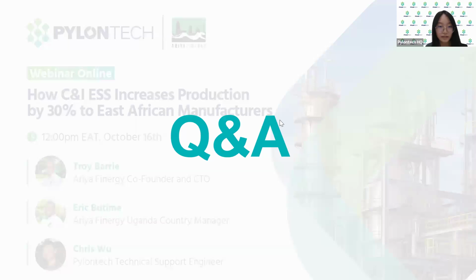Next question from Drake about how we carry out module level and rack level calibration. When we deliver the system to the customer, we already do the debugging and commissioning, making sure all module voltage levels are the same. During system running, at the end of the charge and discharge process, the BMS controls the current during each cycle so that each rack has the same level of SOC. By the end of the charge, if one rack reaches 100% SOC while another is at 98% or 99%, the charge current will only go to that rack until all racks reach 100%.